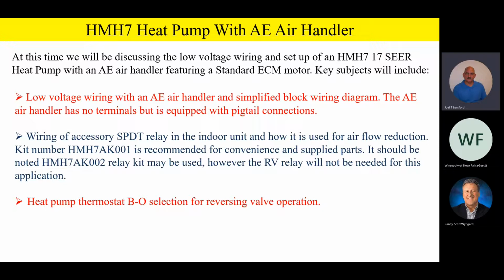In addition, we're going to talk about wiring of the accessory single pole double throw relay in the indoor unit, and how it's going to be used for airflow reduction. So this is a really neat thing. We're going to be reducing the airflow to approximately 60%. When the outdoor unit starts modulating back, it's going to generate a signal for us to operate a relay inside the air handler. Now, it should be noted, kit number HMH7AK001 is recommended for convenience and supplied parts.